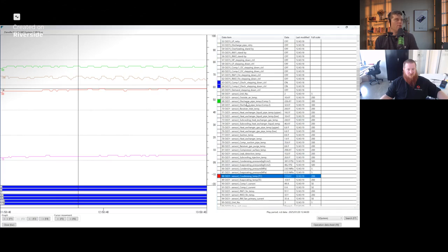Let's go to my favorite thing in the whole wide world. Discharge superheat, right? Discharge superheat is one of those big things. We actually took a poll internally here recently, didn't we? Yeah. What do you look at? We went to the experts of experts, all the people, no names. What do you look at first? And the guys who have been doing this a very long time, discharge superheat is the number one thing we got back that everybody jumps to first.